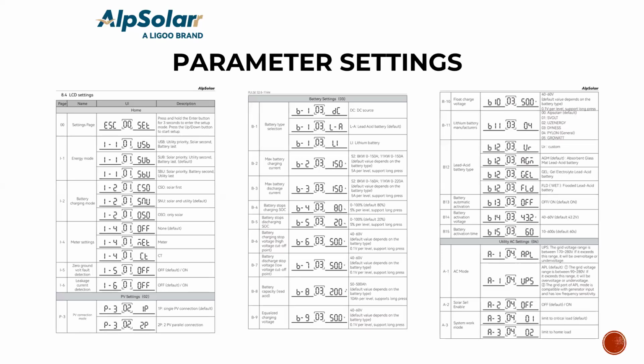And the next thing you want to set is that you press and hold enter button, get to settings mode, navigate down to B1. B1 is where you choose your battery type, whether it is lead acid battery, lithium battery, or DC. Let's say you are using solar panels to power your inverter directly alone, so you choose DC. So you just press enter button. By default, it comes with LA, lead acid battery. So once you connect your battery to the inverter, you have to set it back to lithium.